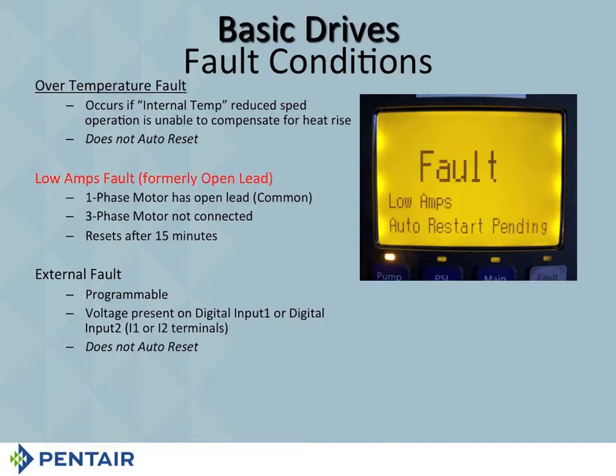Low amps fault, it used to be called the open lead fault. What it basically means is we're not picking up anything on the common, so we're putting electricity down, we're not bringing electricity back, or our three-phase isn't connected properly. It will try to reset after 15 minutes, and again, it could fault out again, okay?